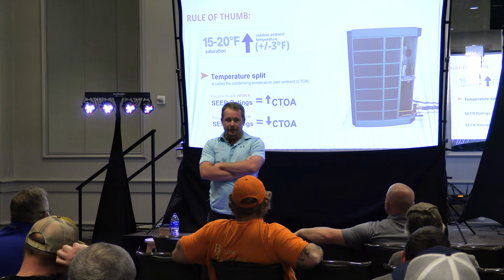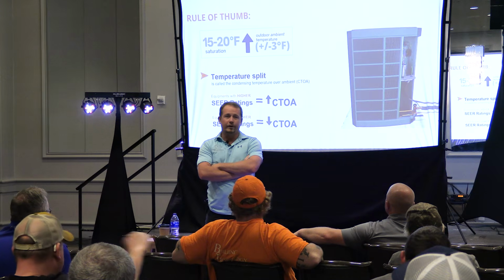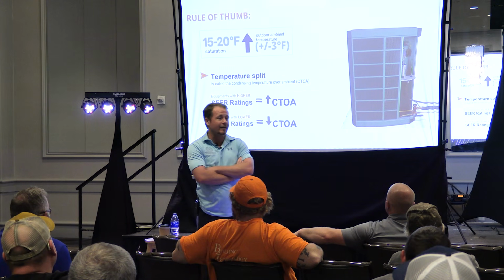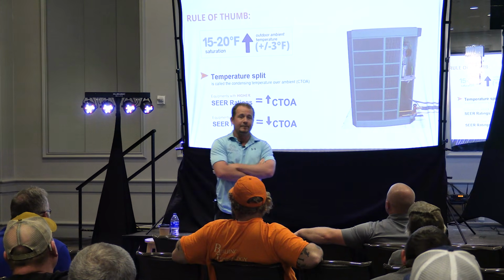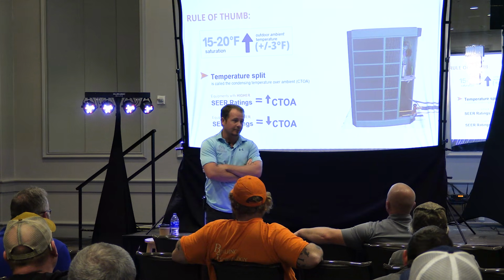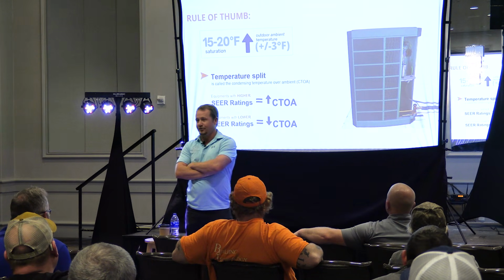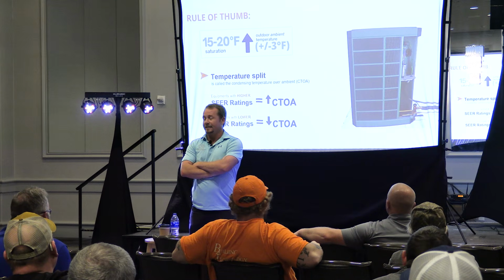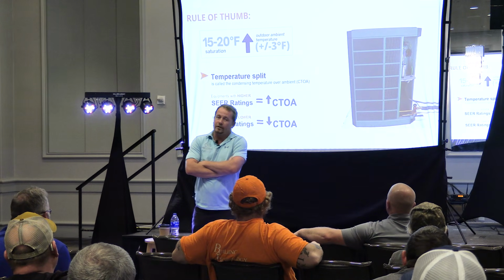When I first started in the trade, that whole 30 degree over ambient head pressure was actually the way I was taught to charge systems in trade school. They didn't teach me superheat and subcool. They taught 30 degrees over ambient discharge. That's the standard way they taught it. And in refrigeration, that still holds true in a lot of systems.